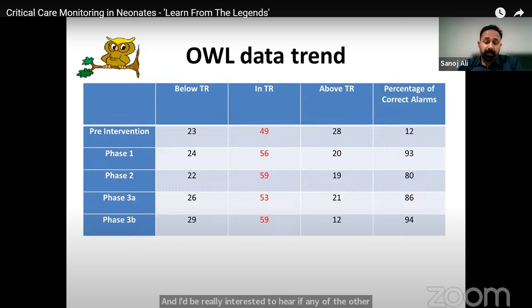So let's look into a few of the basics of automated oxygen control. When you look at it, it's fairly simple. We have a set of SpO2 readings going from the oximeter at regular intervals, up to 1 second, and they go into a control device, which houses the algorithm. The algorithm tries to target the midpoint. So if our SATS target is 91 to 95, it always tries to keep the baby's SATS around 93%, so it constantly adjusts the FiO2 second by second. And subsequently, we have an FiO2 response.